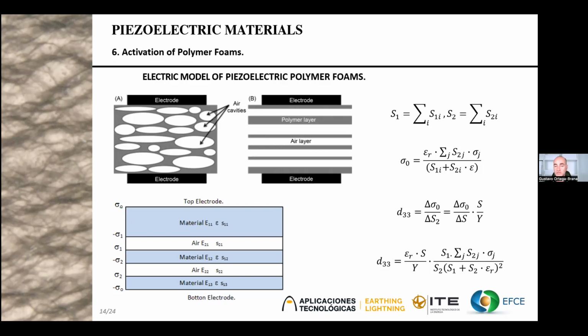The quantity of charge on the electrode depends on the variation of the thickness of the material when a force is applied on it. Also, it is a function of the permittivity of the polymer, but the only part that moves in this material is the air, because the polymer is incompressible. So the d33 charge per Newton of force will be the charge density sigma that we see in this equation, divided by the Young modulus, resulting in the d33 equation, which is the response of the piezoelectric material in picocoulombs per Newton.